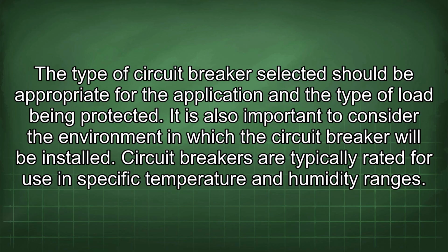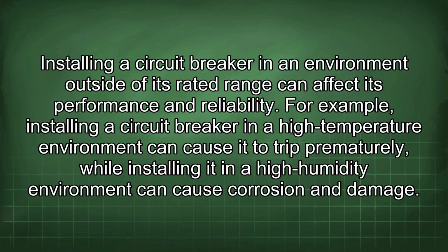It is also important to consider the environment in which the circuit breaker will be installed. Circuit breakers are typically rated for use in specific temperature and humidity ranges. Installing a circuit breaker in an environment outside of its rated range can affect its performance and reliability. For example, installing a circuit breaker in a high-temperature environment can cause it to trip prematurely, while installing it in a high-humidity environment can cause corrosion and damage.